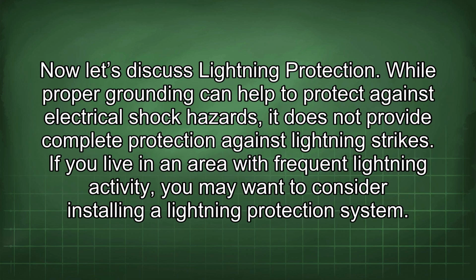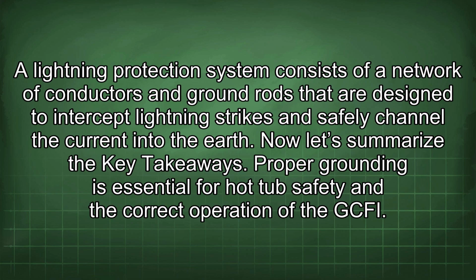Now let's discuss lightning protection. While proper grounding can help to protect against electrical shock hazards, it does not provide complete protection against lightning strikes. If you live in an area with frequent lightning activity, you may want to consider installing a lightning protection system. A lightning protection system consists of a network of conductors and ground rods that are designed to intercept lightning strikes and safely channel the current into the earth.